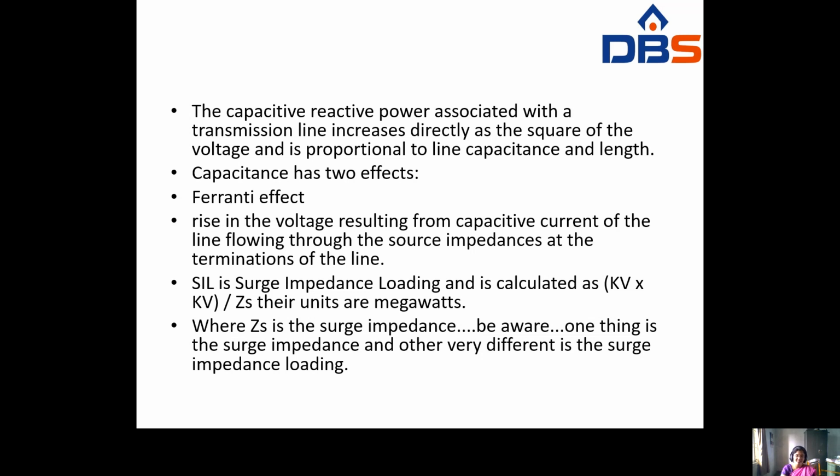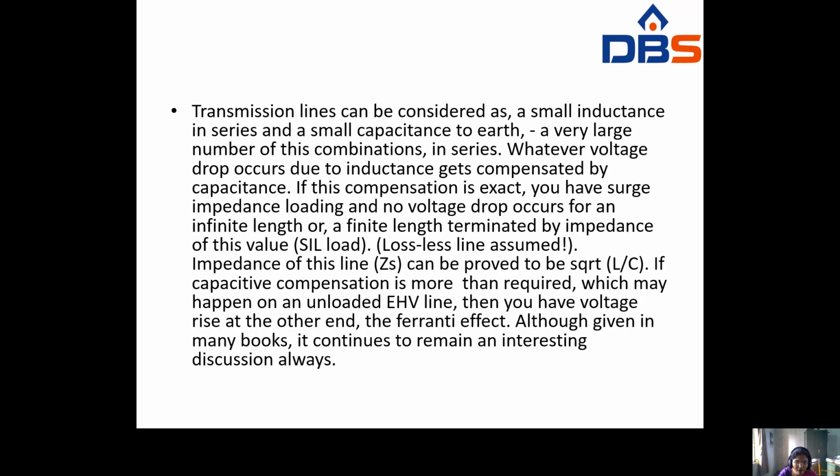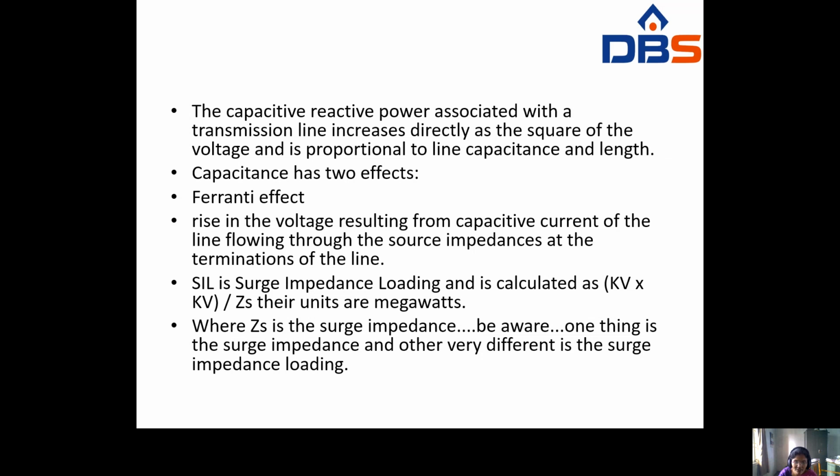Here the capacitance has two effects. One of the effects is the Ferranti effect. What is it? It is the rise in the voltage resulting from the capacitive current of the line flowing through the source impedances at the terminations of the line.